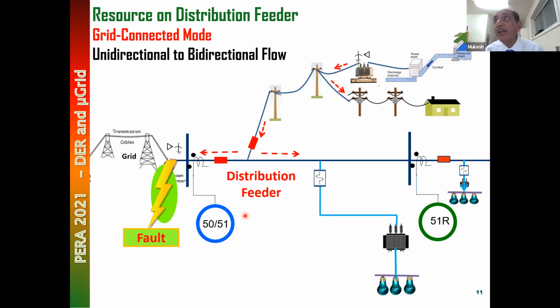That's point number one. Point number two: if the fault is here, in reverse, now you have a bidirectional power flow. This protection was originally designed to operate in this direction. It's a non-directional protection. If the fault happens to be here and the fault current is not high enough, because this resource is so weak, then you have a problem. You need to assess it. You may have to put in a very sensitive directional protection looking this way, depending on this distribution resource, so that it can detect faults in the reverse direction.